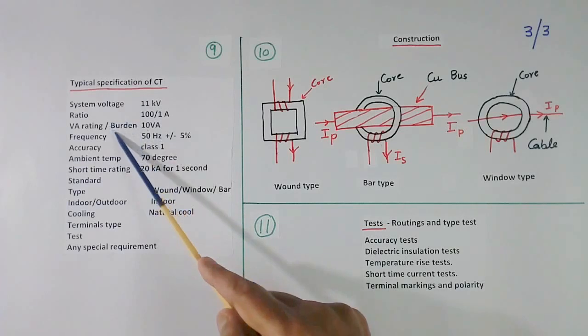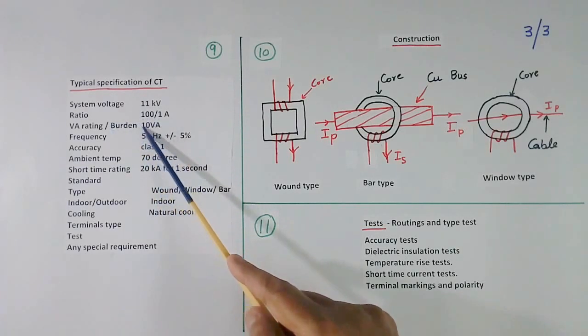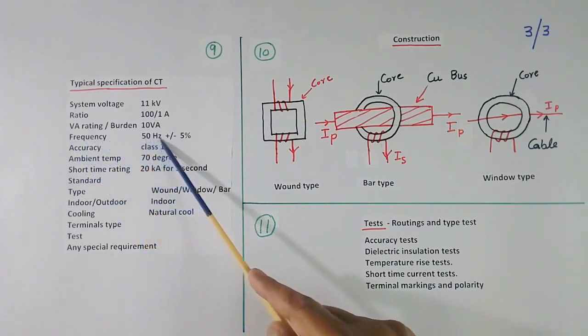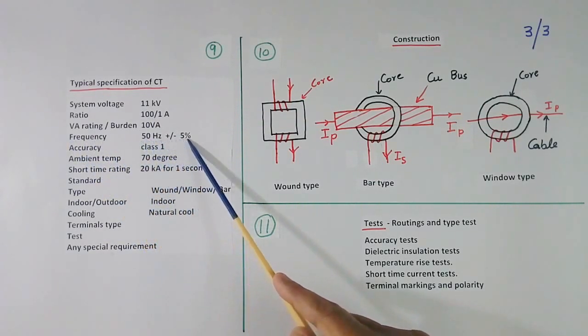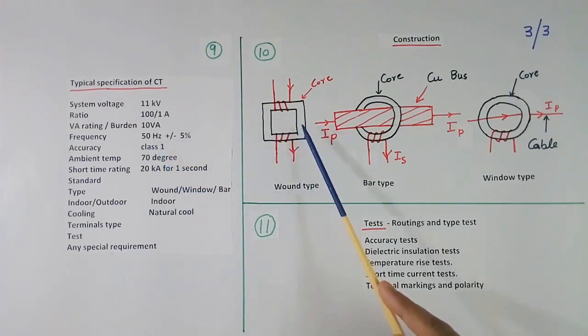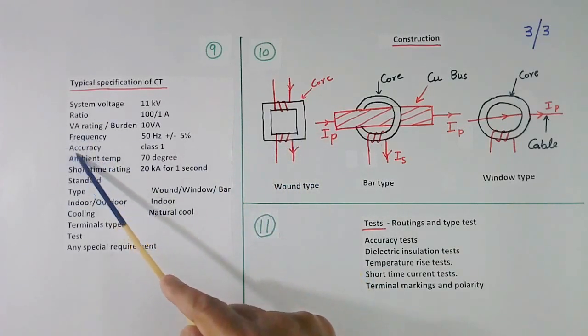Then we should know VA rating. This is called burden also. 10 VA I have written here. Then we have to tell frequency also, 50 Hz plus tolerance also. Lower the frequency, bigger the size of the core will be.